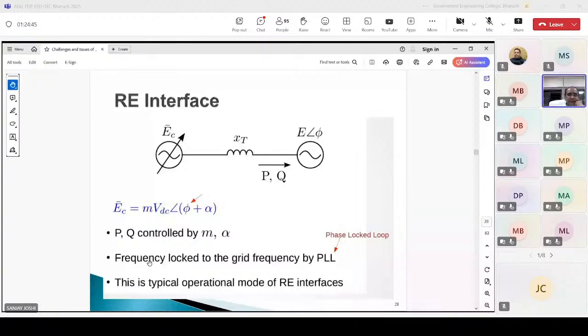An important point here is frequency is locked to the grid frequency by the PLL, so phase lock loop is very important and it has to be there. This is a typical operational mode of RE interfaces, what typically happens in our grid at different RE plants.